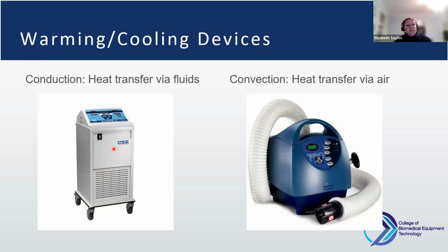So your maintenance on these devices is going to be pretty frequent. The devices we have at one of our locations are actually every 14 days, and Biomed doesn't do the actual cleaning of these devices just because of the rigorous cleaning cycle required. We do everything but the actual disinfection of these units. But like the Cincinnati Sub-Zero devices, it might be every quarter or every 6 months. Really depends on what the manufacturer recommends.